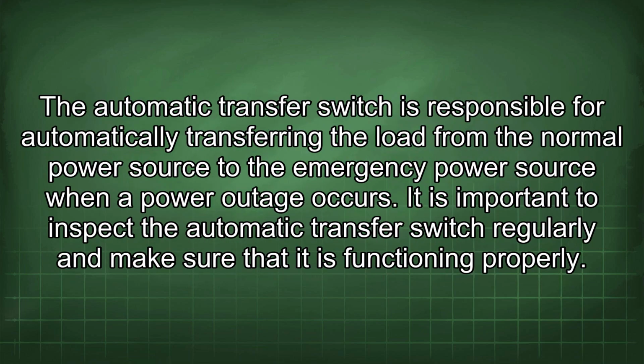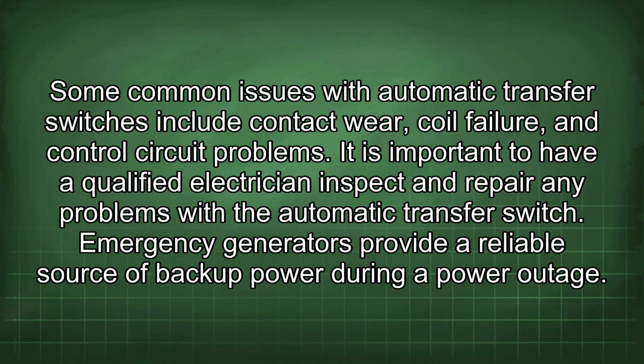The automatic transfer switch is responsible for automatically transferring the load from the normal power source to the emergency power source when a power outage occurs. It is important to inspect the automatic transfer switch regularly and make sure that it is functioning properly. Some common issues with automatic transfer switches include contact wear, coil failure, and control circuit problems. It is important to have a qualified electrician inspect and repair any problems with the automatic transfer switch.